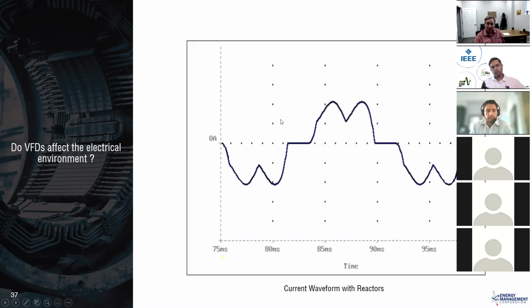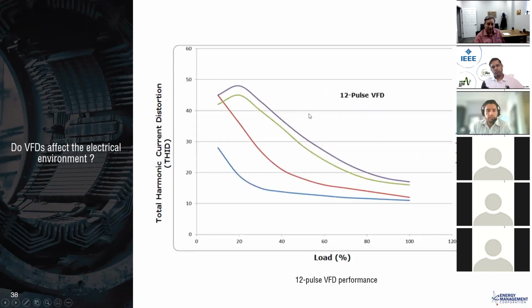This is more typical when you have a reactor. It smooths out a little bit. The previous one could be up to 100% or more distortion, meaning that more of the current is distorted than is fundamental 60 hertz. This is probably between 30 and 40%. I'm going to run through these very quickly.